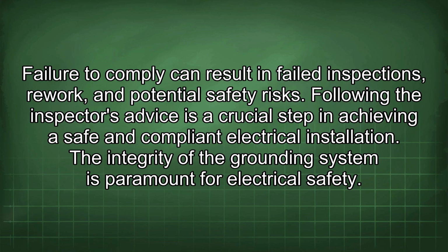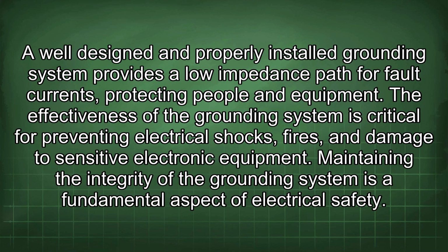Failure to comply can result in failed inspections, rework, and potential safety risks. Following the inspector's advice is a crucial step in achieving a safe and compliant electrical installation. The integrity of the grounding system is paramount for electrical safety. A well-designed and properly installed grounding system provides a low-impedance path for fault currents, protecting people and equipment. The effectiveness of the grounding system is critical for preventing electrical shocks, fires, and damage to sensitive electronic equipment. Maintaining the integrity of the grounding system is a fundamental aspect of electrical safety.